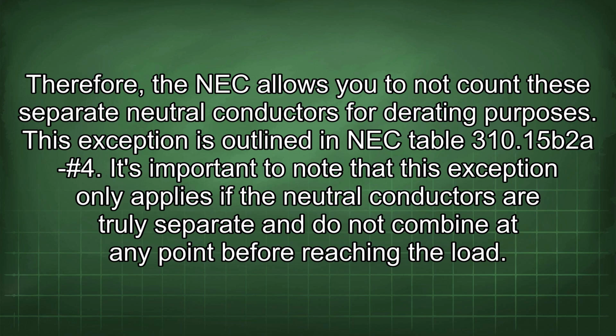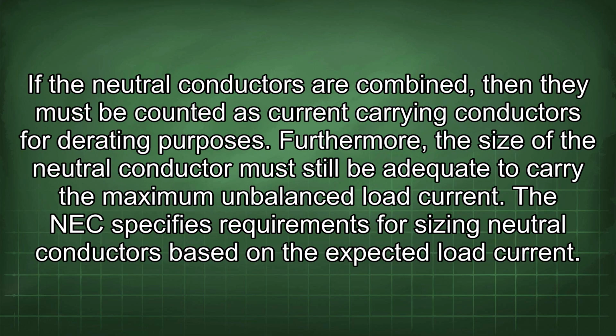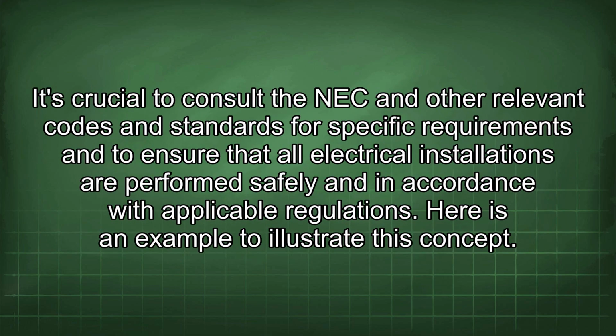This exception is outlined in NEC Table 310.15(B)(2)(a)-#4. It's important to note that this exception only applies if the neutral conductors are truly separate and do not combine at any point before reaching the load. If the neutral conductors are combined, then they must be counted as current-carrying conductors for derating purposes. Furthermore, the size of the neutral conductor must still be adequate to carry the maximum unbalanced load current. The NEC specifies requirements for sizing neutral conductors based on the expected load current. It's crucial to consult the NEC and other relevant codes and standards for specific requirements and to ensure that all electrical installations are performed safely and in accordance with applicable regulations.